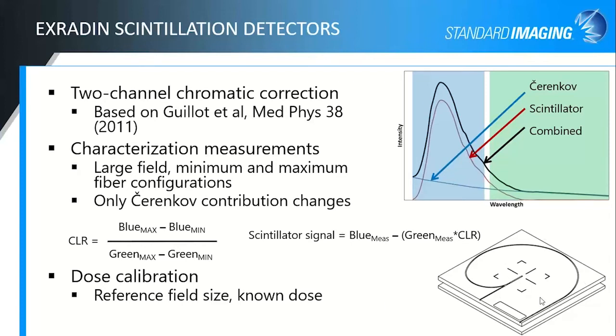This is the characterization jig that comes with the W1. We have a smaller one for the W2 that can be used in a water tank. But essentially, you do 2 measurements, one with the scintillation fiber coming straight out, which we call the minimum fiber configuration, and one with the fiber wrapped all the way around in this channel, which we call the maximum fiber configuration. And you irradiate it with a larger field, like a 30 by 30 field, to cover this whole plastic phantom. For the smaller bracket that we use for the W2, you can do it in a 10 by 10.